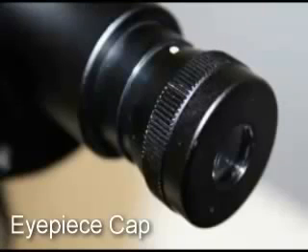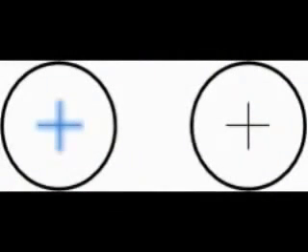After you focus the eyepiece, turn the instrument on and look through the eyepiece. You will see a plus sign. Continue looking through the eyepiece and turn the eyepiece cap clockwise until the plus sign becomes sharp and in focus. Do not turn the eyepiece cap back and forth, as this will stimulate accommodation.